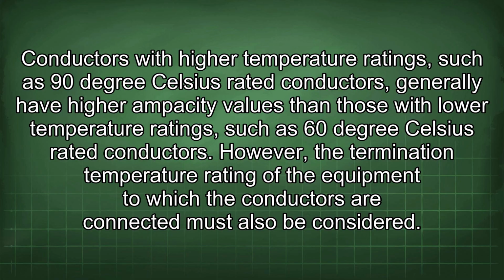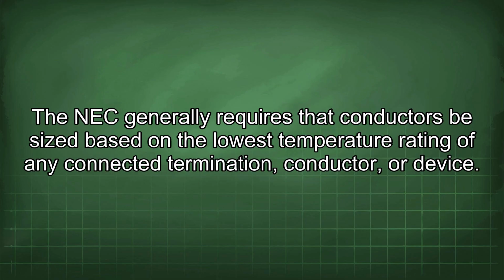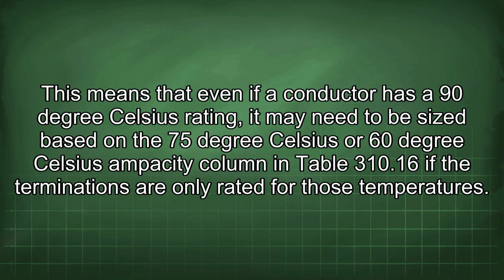However, the termination temperature rating of the equipment to which the conductors are connected must also be considered. The NEC generally requires that conductors be sized based on the lowest temperature rating of any connected termination, conductor, or device. This means that even if a conductor has a 90 degrees Celsius rating, it may need to be sized based on the 75 degrees Celsius or 60 degrees Celsius ampacity column in Table 310.16 if the terminations are only rated for those temperatures.